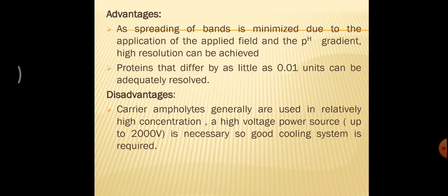The disadvantage is that the carrier ampholytes are generally used at relatively high concentration. A high voltage power source of up to 2000 volts is necessary, and a good cooling system is required here. Because we are applying high voltage, it generates heat. So in order to cool it, it is necessary to make an arrangement for a cooling system.